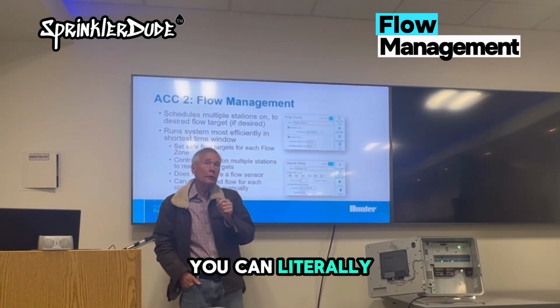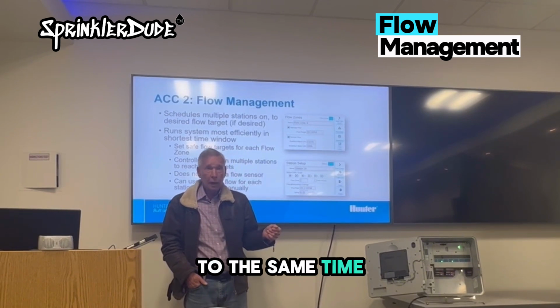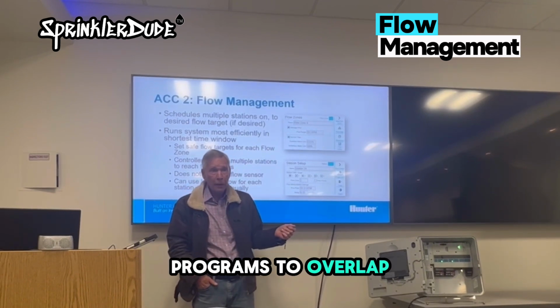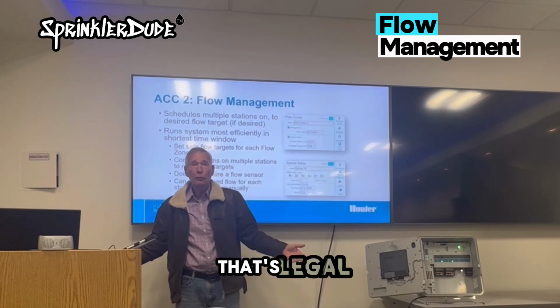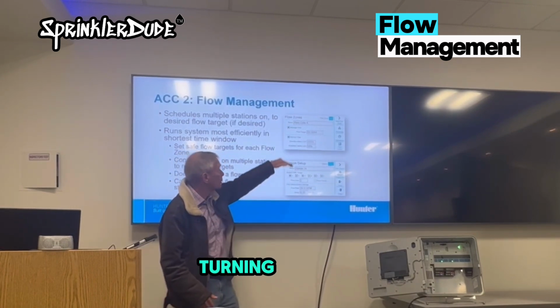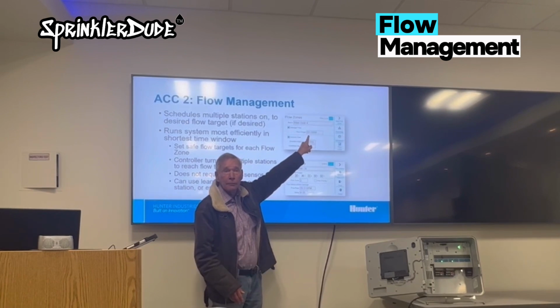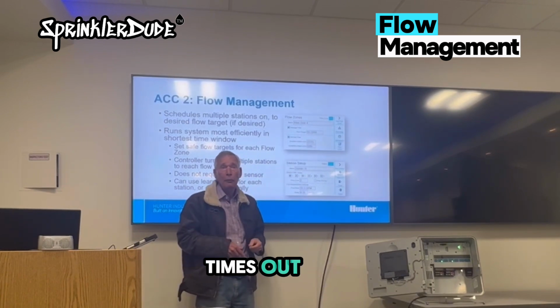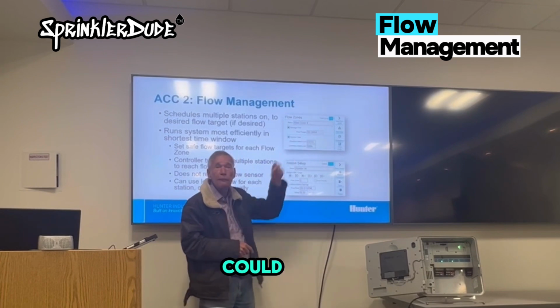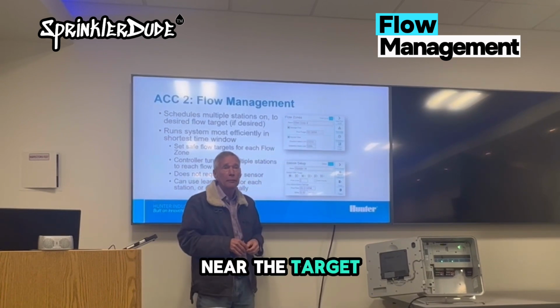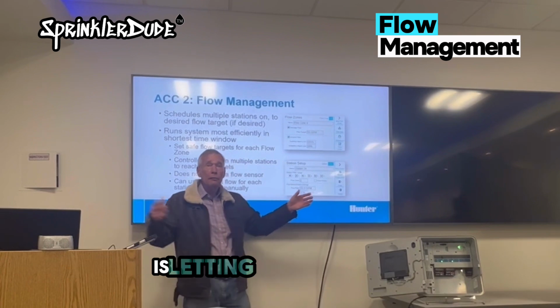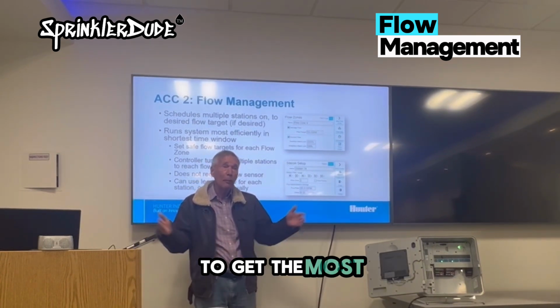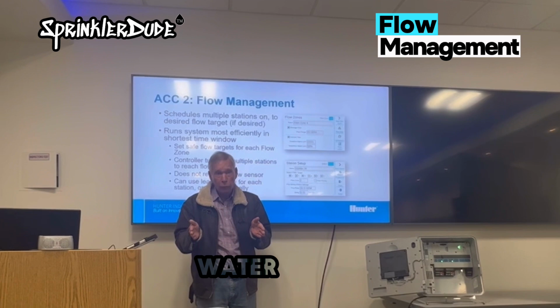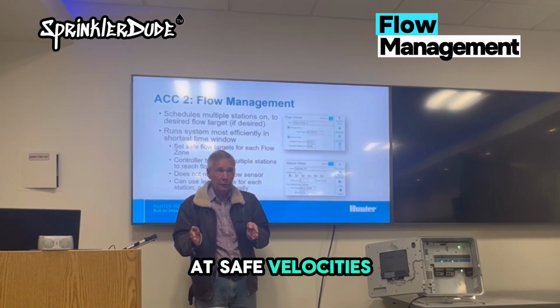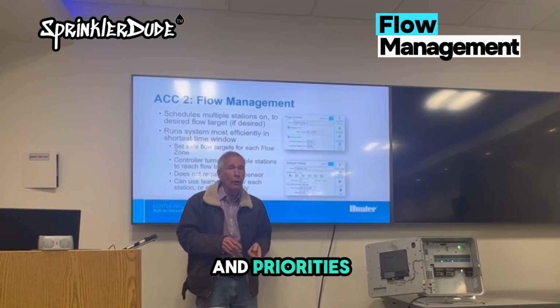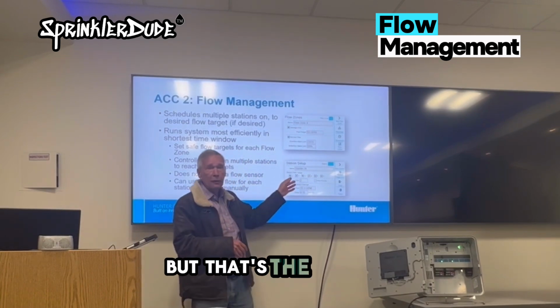Here, you can literally set all of your start times to the same time, set all your programs to overlap. It gives him every station that's legal to run today. He'll start turning them on until he gets to your target. When one of those stations times out, he'll look for another station that he could fit in to keep it up near the target. And what you're doing is letting the controller figure out how to get the most irrigation done in the shortest water window at safe velocities. You can put other controls and priorities, get as fancy as you want, but that's the concept.